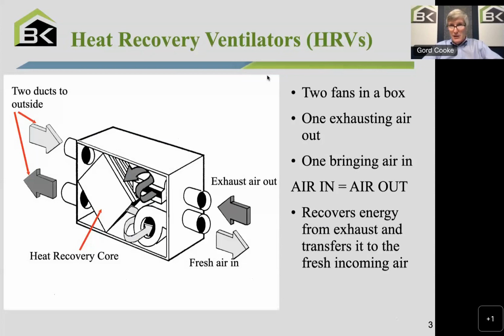And that might be a little instructive just to do some simple math and say, for example, if it's 20 degrees Celsius inside and it's minus 20 degrees Celsius outside, that's a temperature difference of 40 degrees. So the air wants to come in at minus 20. As it comes across this device, it gets warmed up by 80%. 80% of 40 degrees, 32 degrees. So the air starts at minus 20, comes through the heat recovery core, gets warmed up by 32 degrees, which means it comes into the house at 12 degrees Celsius.